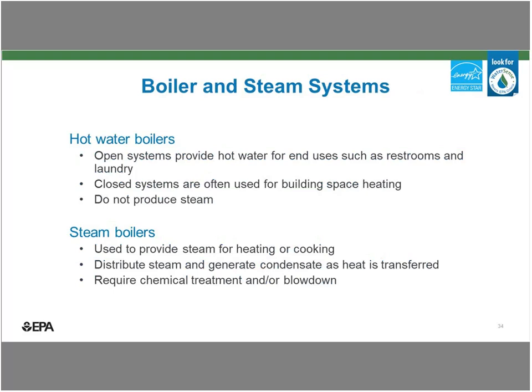There are really two main types of boilers. There's hot water boilers and there's steam boilers. Hot water boilers are either open systems that produce hot water for domestic consumption or laundry operations, or they can be recirculating closed systems that are typically used for space heating. Domestic hot water efficiency is mainly related to the efficiency of the water use. So installing high efficiency WaterSense labeled faucets, shower heads, laundry systems will help you save water and energy. Recirculating closed hot water systems are for space heating. Those should, similar to a chilled water system, have very little makeup water as well. So the focus of our presentation is really going to be on steam boilers.